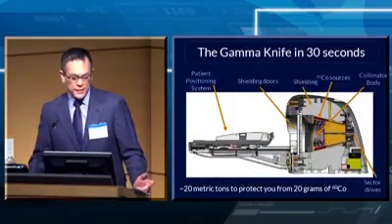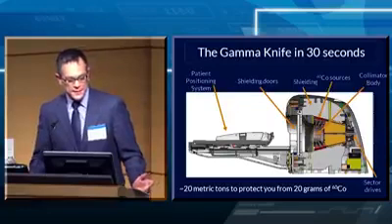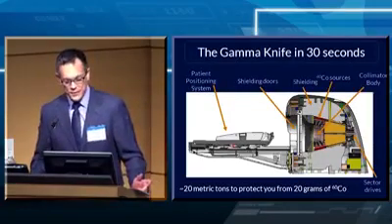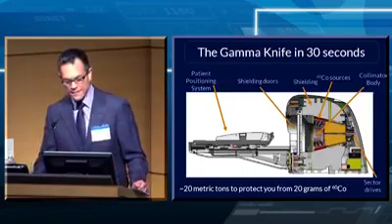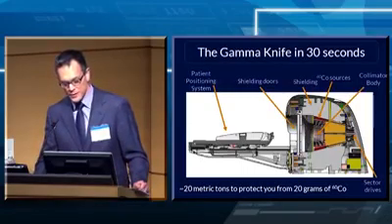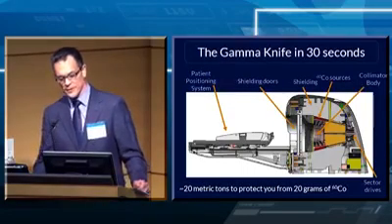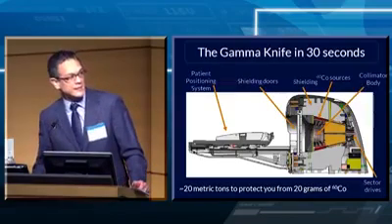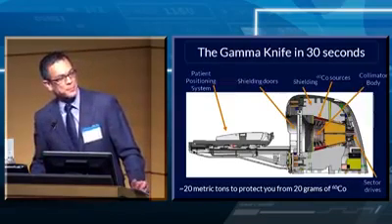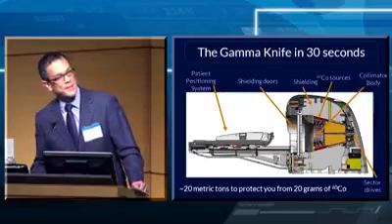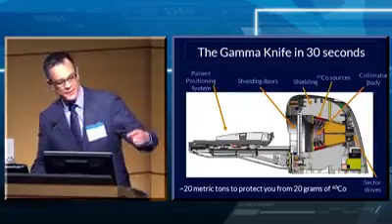So again, cobalt-60 is what runs the Gamma knife. So just to describe a Gamma knife in like 30 seconds, you have 192 cobalt-60 sources that are sort of here and here, but this is a kind of like a styrofoam coffee cup shaped collimator system. So they go all the way around kind of in a cylinder.